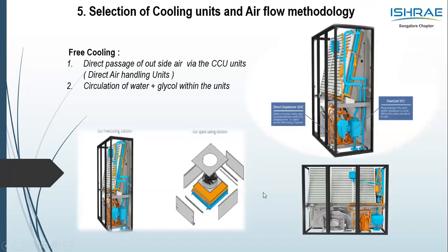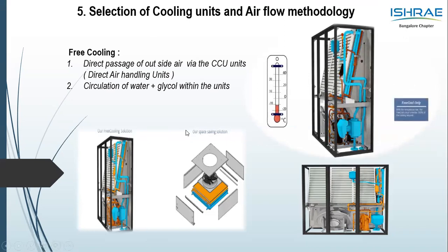The second concept is the free cooling unit, where we don't let the outside air in, but we get the benefit of the lower ambient, where a separate circuit is placed within the CCU with a circulation of water and ethylene glycol. As the temperature is low, it is only free cooling, where the circuit of water and glycol circulates without the DX. As the ambient temperature increases, it goes into a mixed mode. What is mixed mode? It is a combination of this circuit with a small AC pump and partial DX, or it can also be a chilled water. And as the temperature further increases, then it goes only into a DX mode.